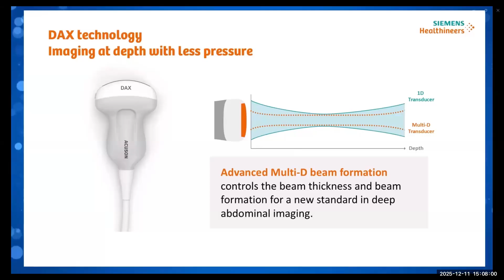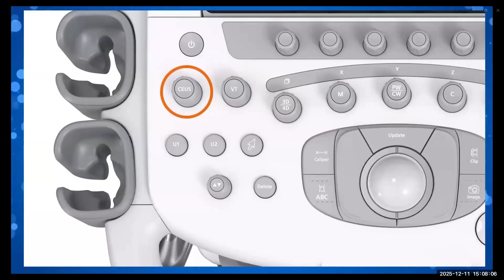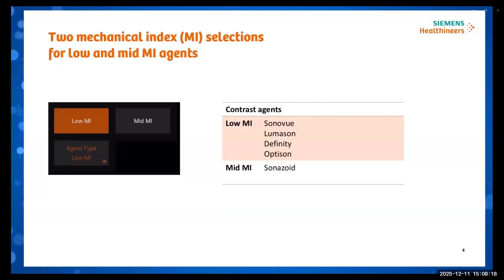Let's explore some contrast controls of the Acuson Sequoia ultrasound system. Pressing the CEUS button will start the contrast study. Two unique features of the Acuson Sequoia for contrast imaging are, firstly, that the system allows users to set the maximum mechanical index in the field of view, which prevents bubble destruction independent of focal depth. And secondly, the system allows users to select a preset for different types of contrast agents to best optimize their contrast images.